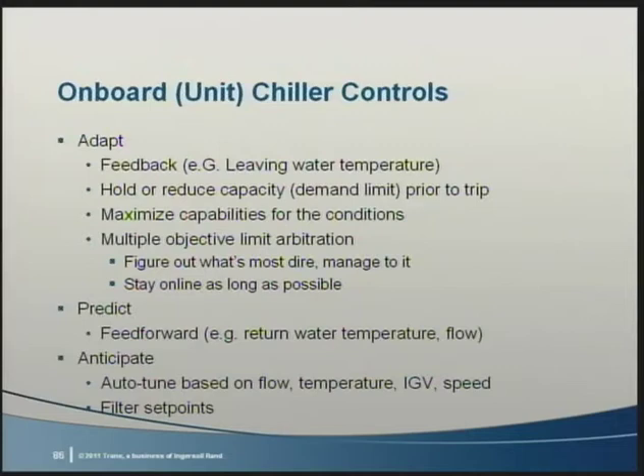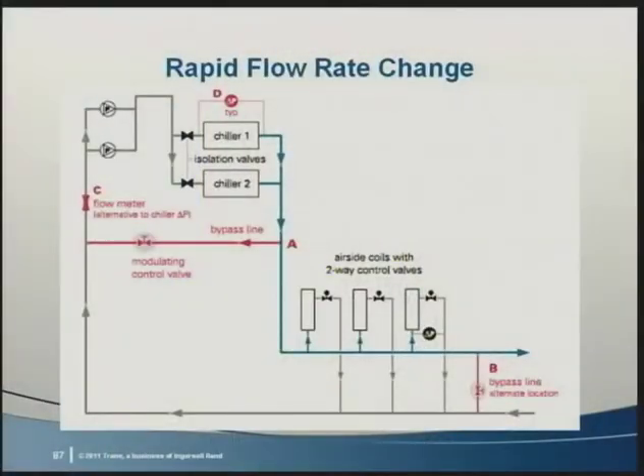You want your controls to be able to communicate with your BAS and provide the sequencing necessary. So keep in mind that it may be necessary to include this controls upgrade in your analysis. Typically, older systems do not have the unit controls necessary to react to the evaporator flow variation. To illustrate this old control deficiency, let's look at a rapidly changing flow situation. Here's our layout after converting to a variable primary flow 2-chiller system. Transitioning from 1 chiller operating to 2 chillers is the hardest.